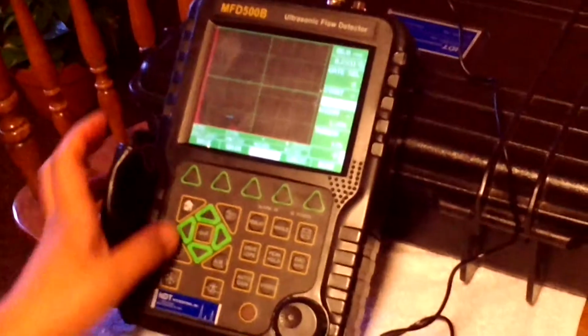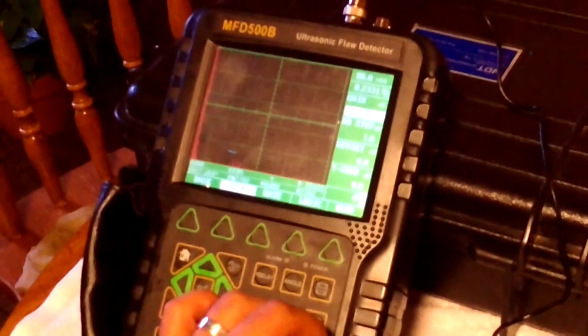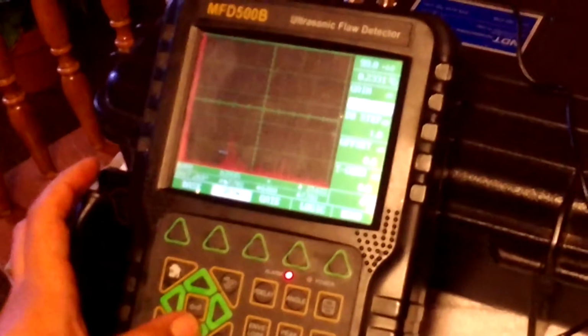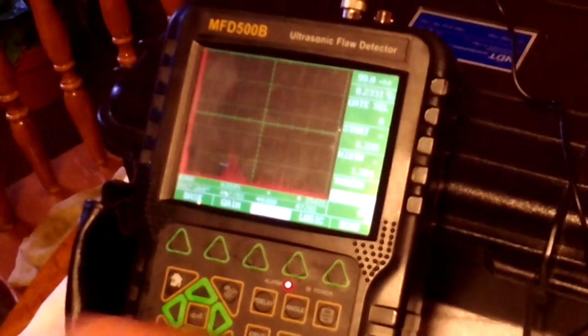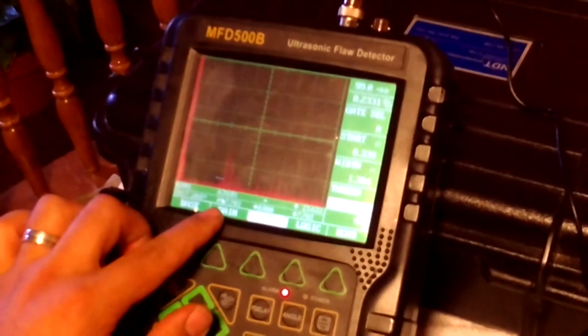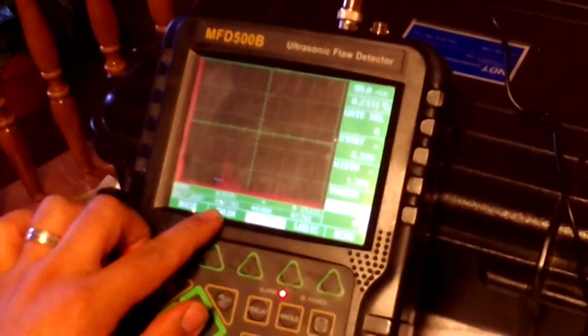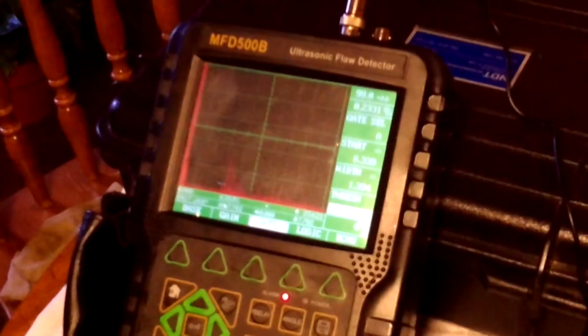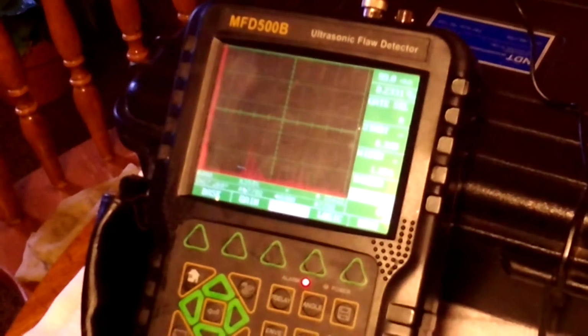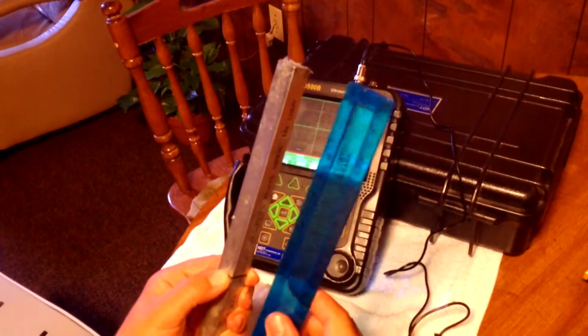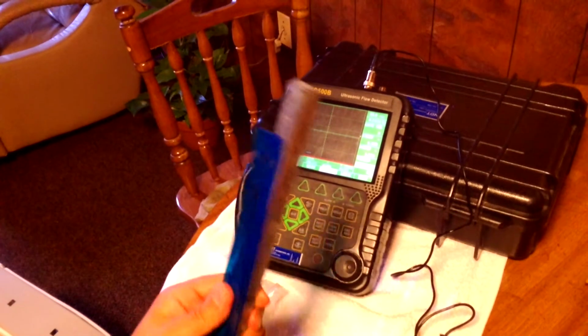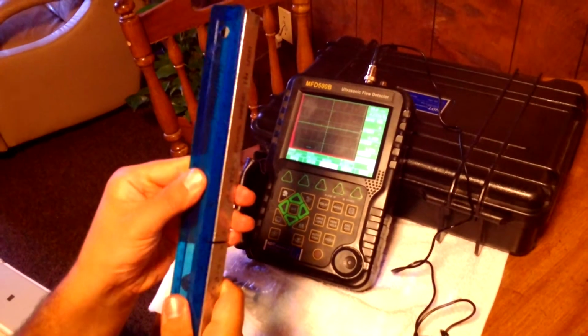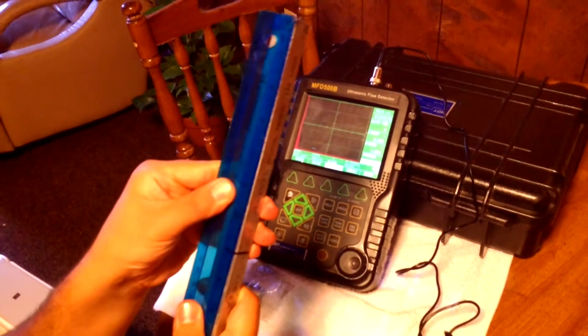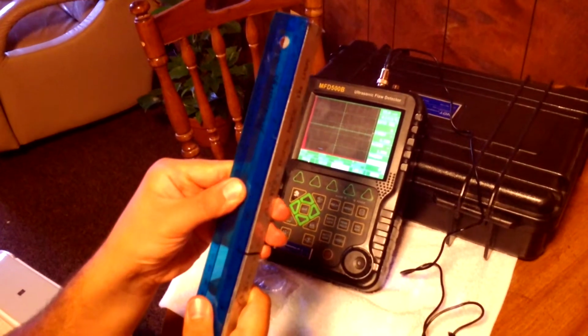As you can see, the echo has a much lower amplitude, so I increase my gain, and now I try to catch that echo with my gate, and it's saying the echo is coming back at a distance of 7.7 inches. So there is an anomaly or a discontinuity, and it should be at 7.7 inches. Let's go ahead and measure that. As you can see, it is almost at that distance, 7.7 inches.